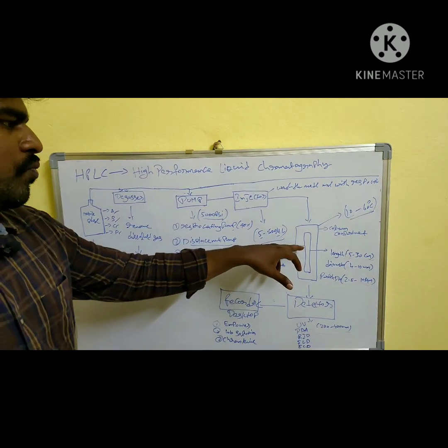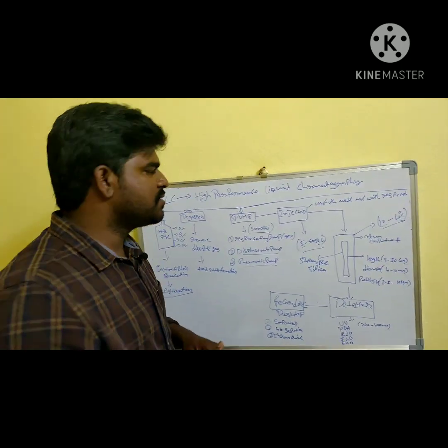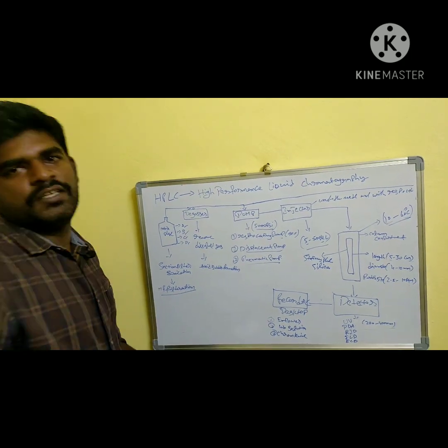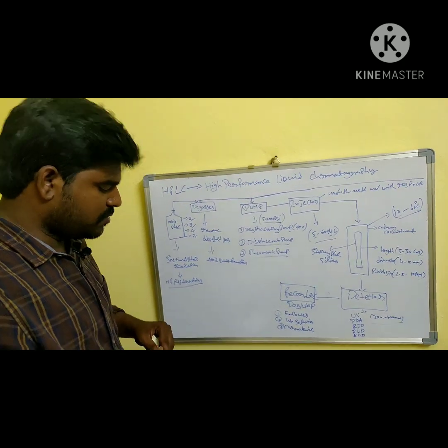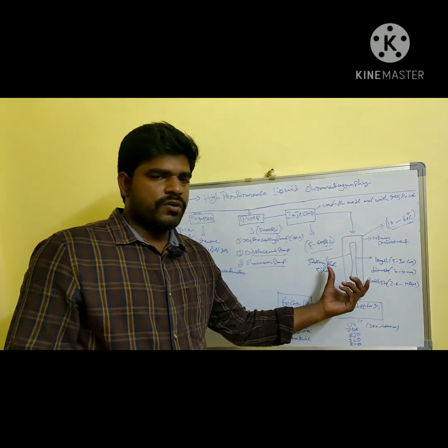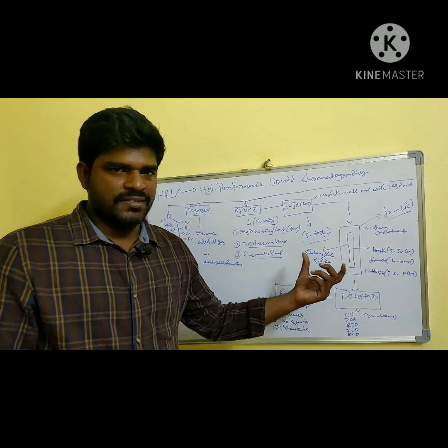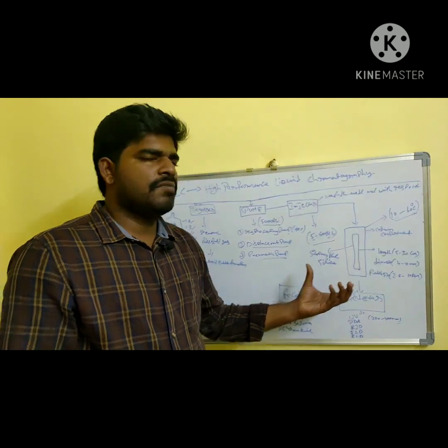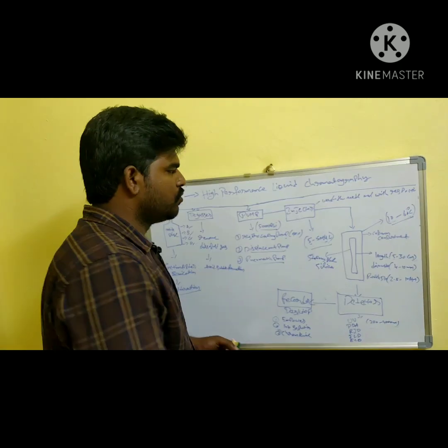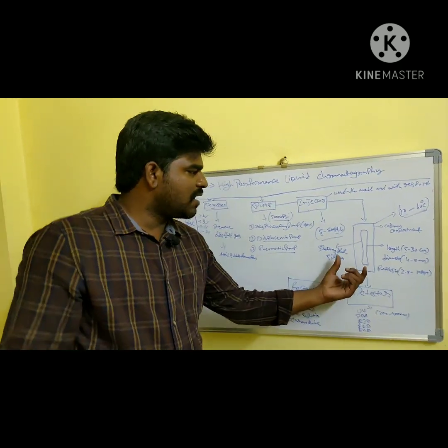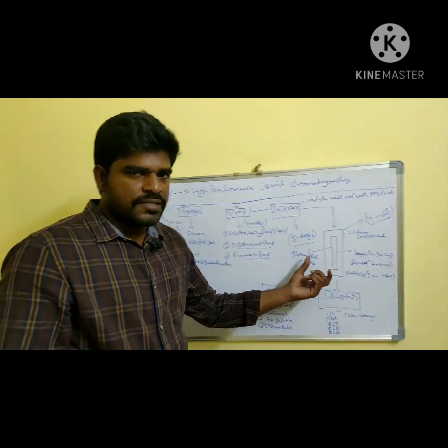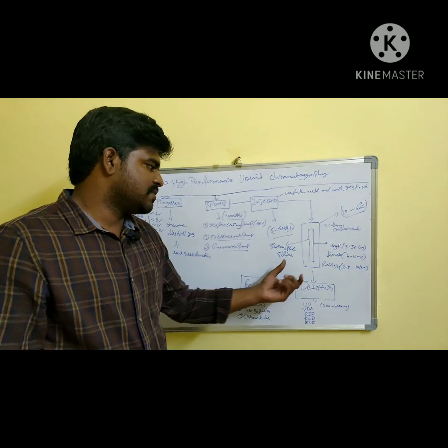The next most important thing is proper washing of the column before and after the analysis. Why? Because if you do not wash the column properly, you may get some extra peaks, some humps, and some abnormal results. So to avoid that and increase the life of the column, we need to wash the column with appropriate solvents before and after the analysis.